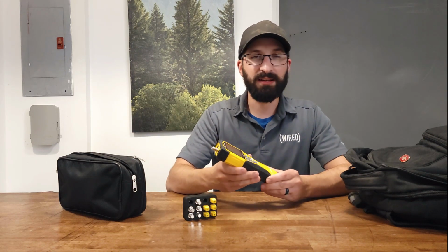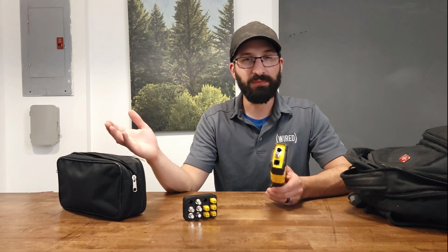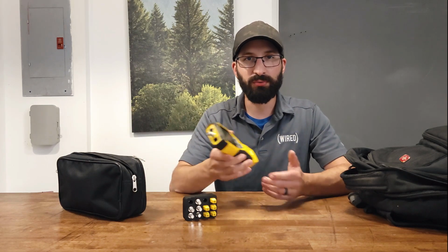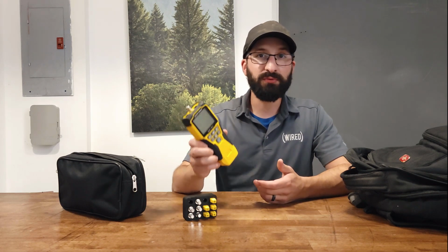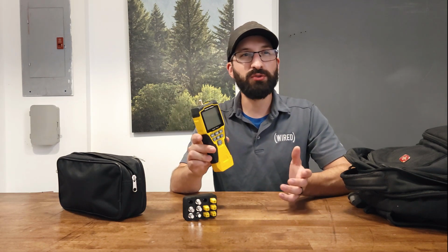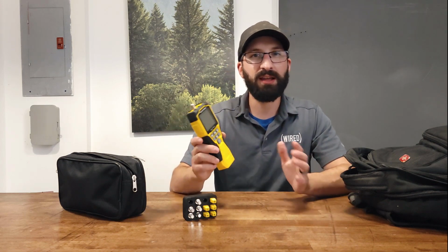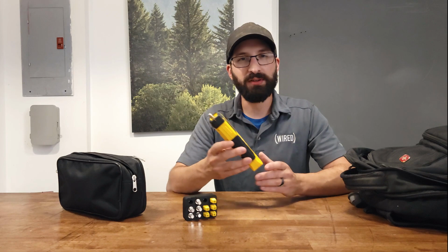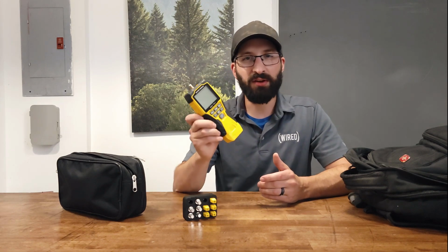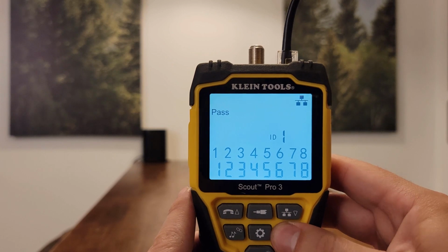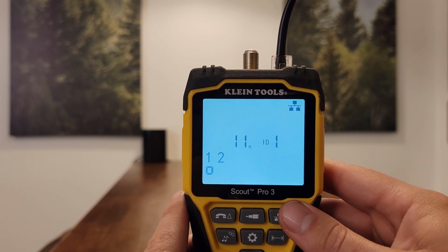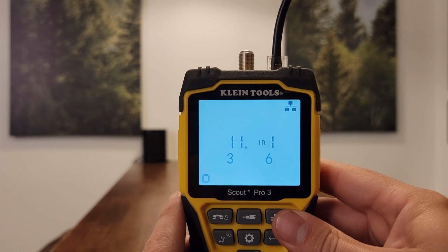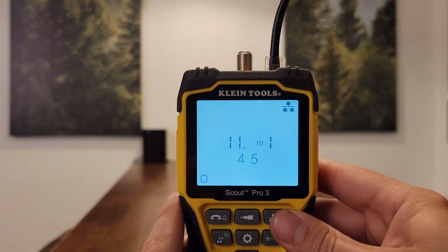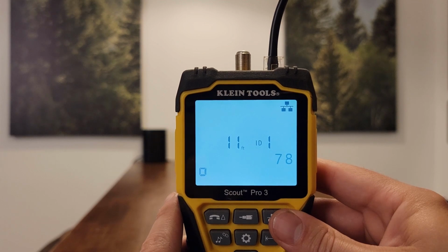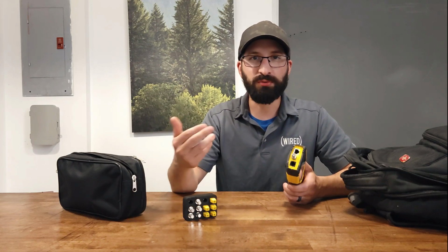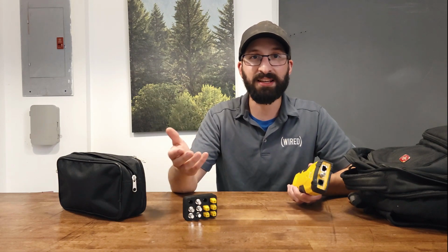That's very handy if you're wanting to verify that your cable run is under 100 meters or 328 feet. It is also very useful if you want to tell where in a cable there's a fault, because it not only tells the distance of the cable, but it also tells the distance of each pair. So if pair 1 and 2 is 100 feet and pair 7 and 8 are 20 feet, then you know you have an issue 20 feet in, and it's only those 2 pairs if all the others are reading the exact same length.